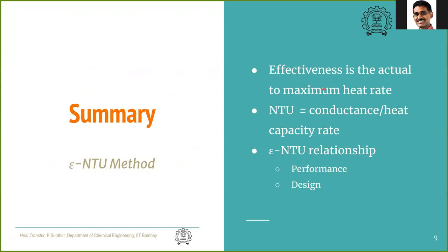To summarize the ε-NTU method: effectiveness ε is the actual heat rate divided by the maximum theoretical heat rate; NTU is defined as conductance UA divided by minimum heat capacity rate C_min. The relationship between ε and NTU for various heat exchanger configurations is available in charts and tables. This relationship is used to calculate either performance — finding outlet temperatures or heat rate — or design, finding the required area.